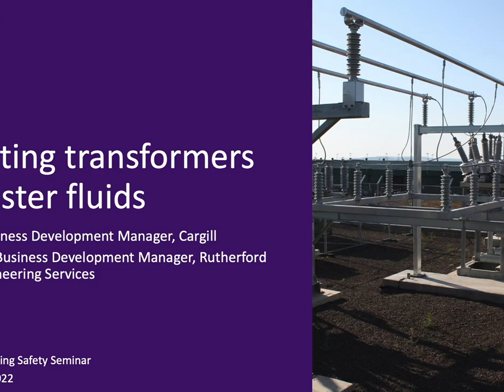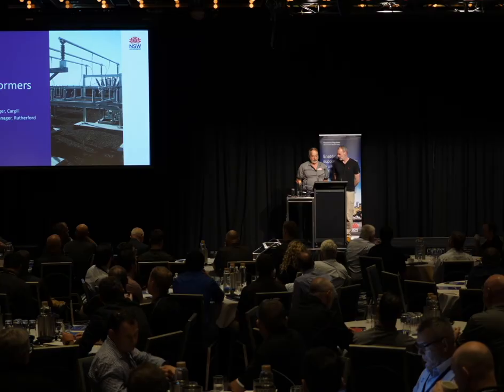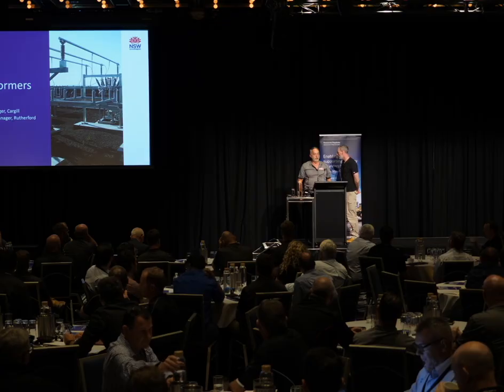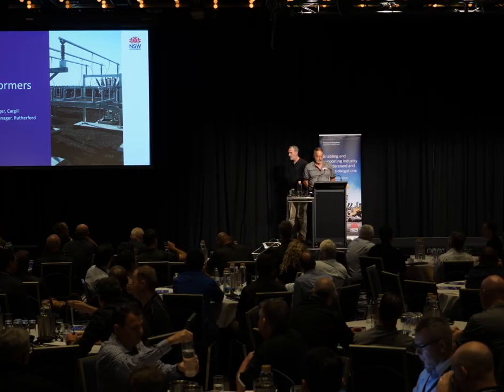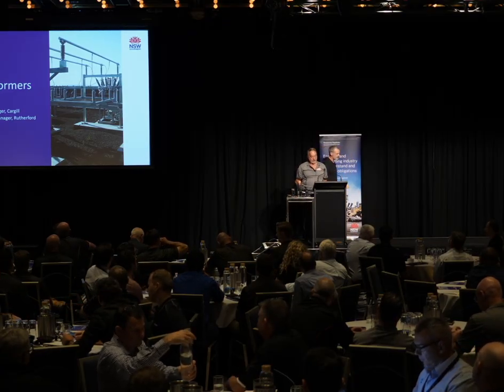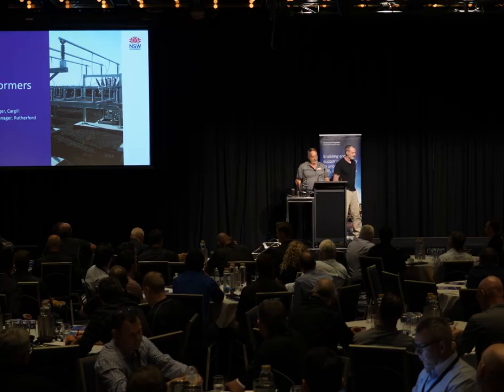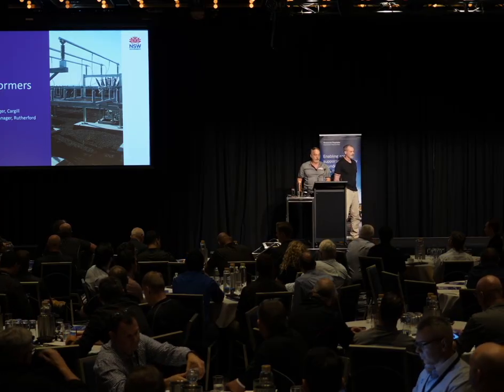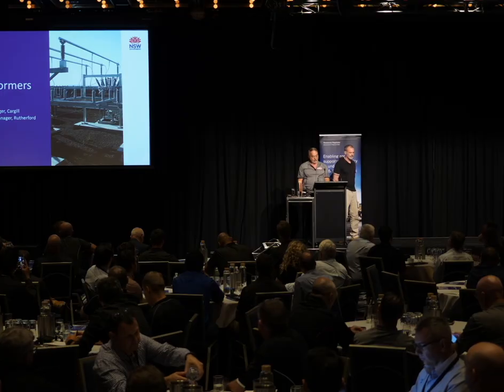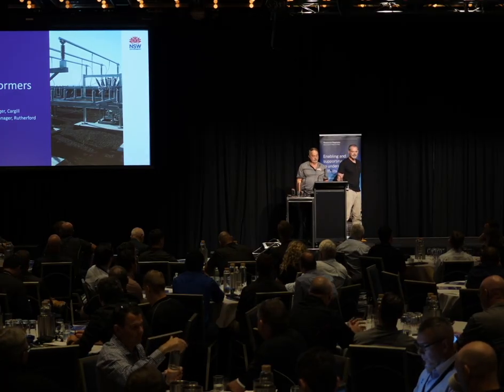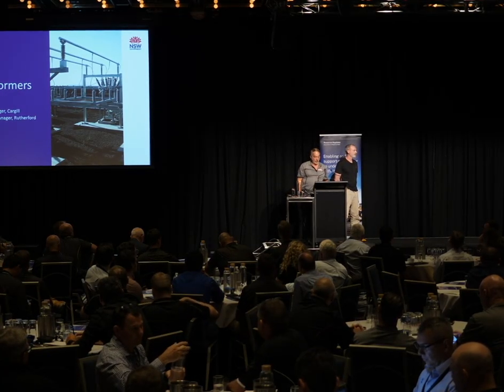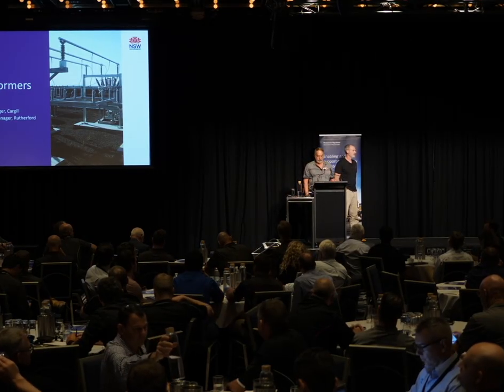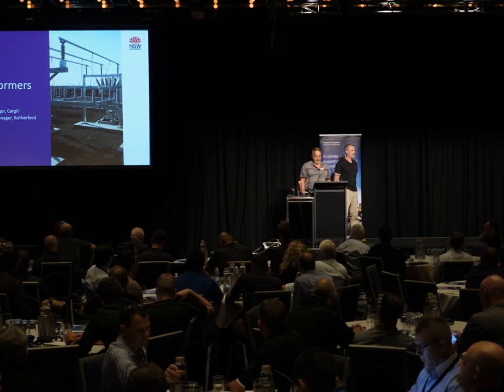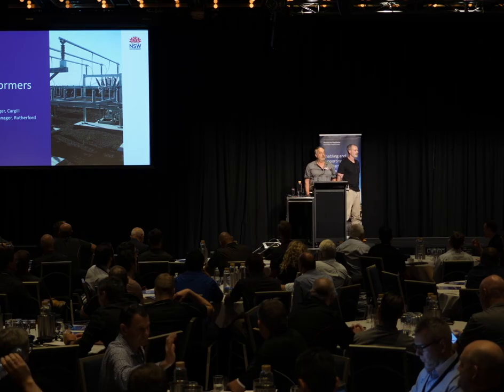As you would be aware, in New South Wales, the insurance companies are now pushing to change towards fluids that are approved K-class. Now, replacing mineral oil in transformers with esters can be an effective way to upgrade fire safety, slow thermal aging of the insulation, lower the environmental risk, and improve short-term overloadability of an otherwise healthy transformer.